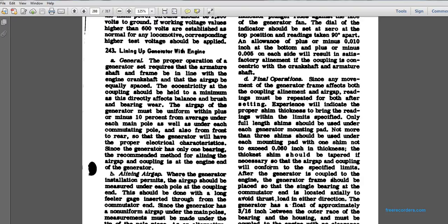243. The lining up of the generator with the engine. Generally, the operation of the generator sets requires the armature shaft to be in line with the engine crankshaft, with the air gap equally spaced. The eccentricity at the coupling should be held to a minimum, as it directly affects balancing, the brush and the bearing wear. The air gap of the generator must be uniform within plus or minus 10% of the average under each main pole as well as under each of the commutating poles. Also, the generator will then have the proper electrical characteristics.